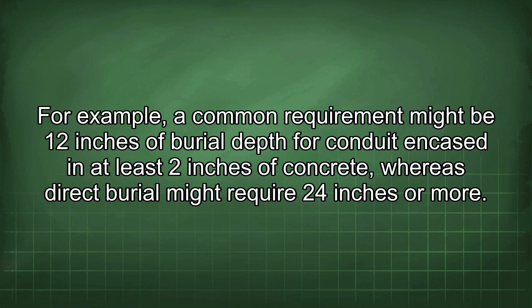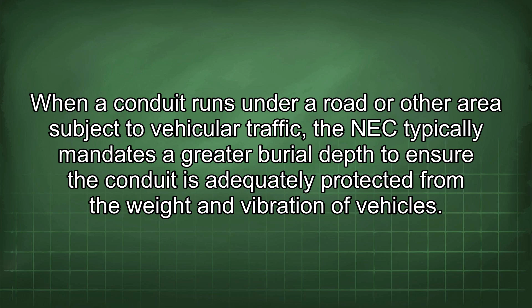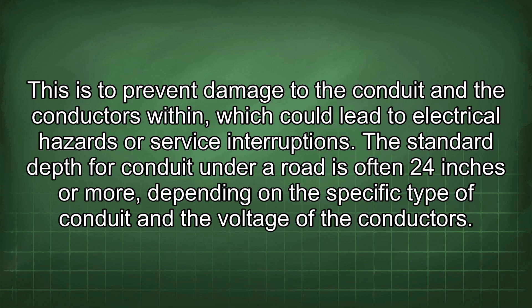When a conduit runs under a road or other area subject to vehicular traffic, the NEC typically mandates a greater burial depth to ensure the conduit is adequately protected from the weight and vibration of vehicles. This is to prevent damage to the conduits and the conductors within, which could lead to electrical hazards or service interruptions. The standard depth for conduit under a road is often 24 inches or more, depending on the specific type of conduit and the voltage of the conductors.